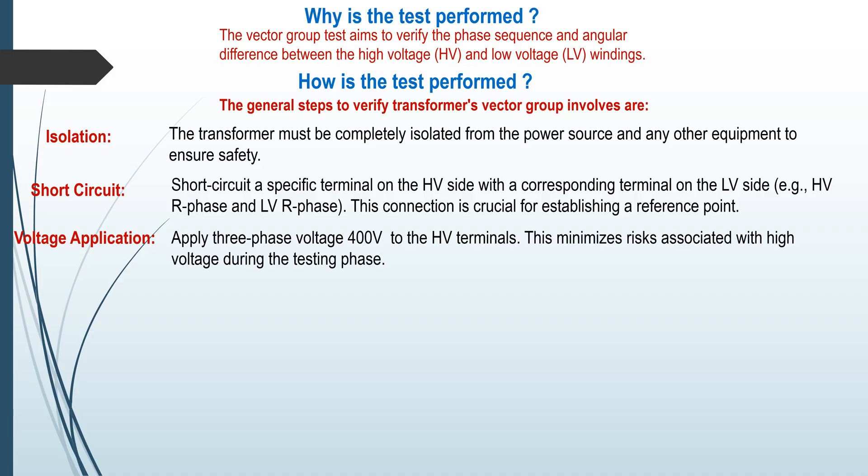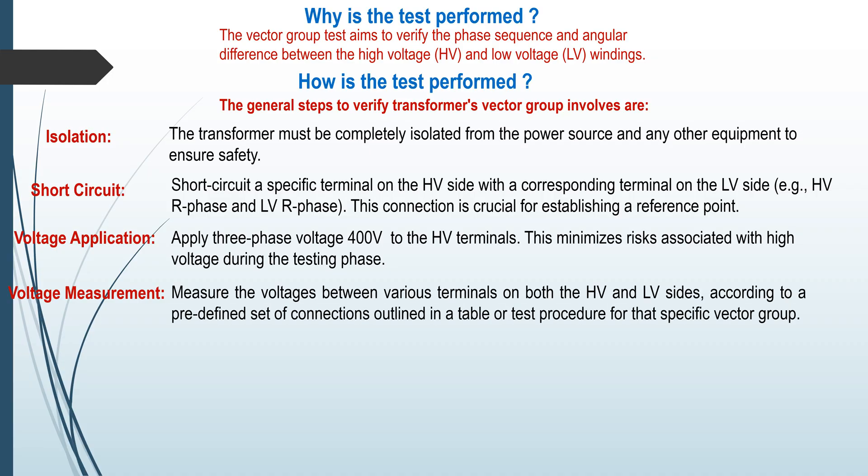Voltage application: Apply 3 phase voltage 400 volt to the HV terminal. This minimizes risks associated with high voltage during the testing phase. Voltage measurement: Measure the voltage between various terminals on both HV and LV sides according to predefined set of connections outlined in a table or test procedure for that specific vector group.